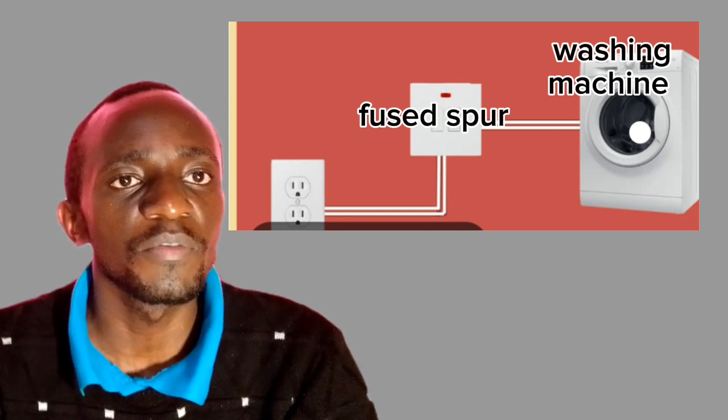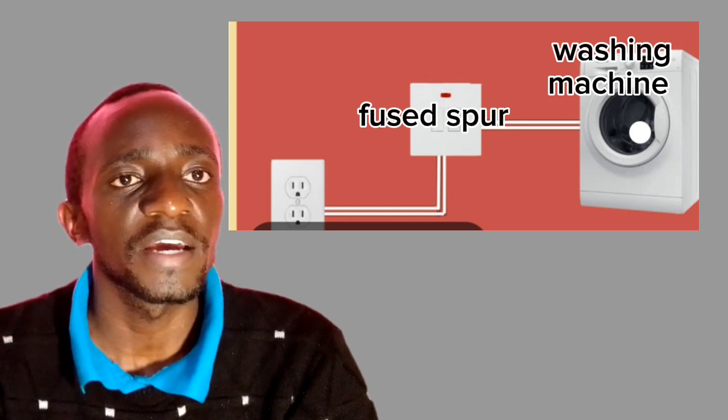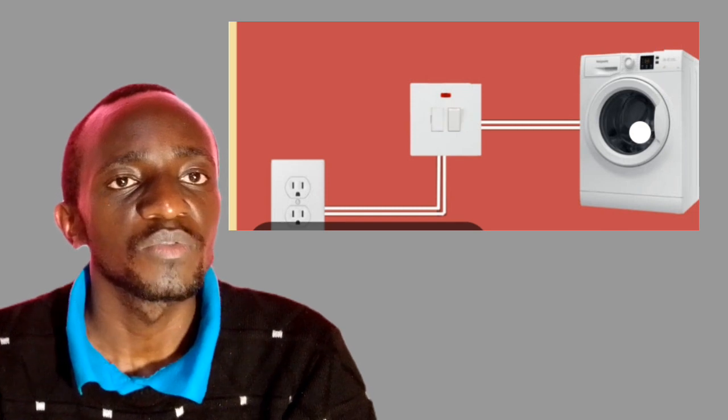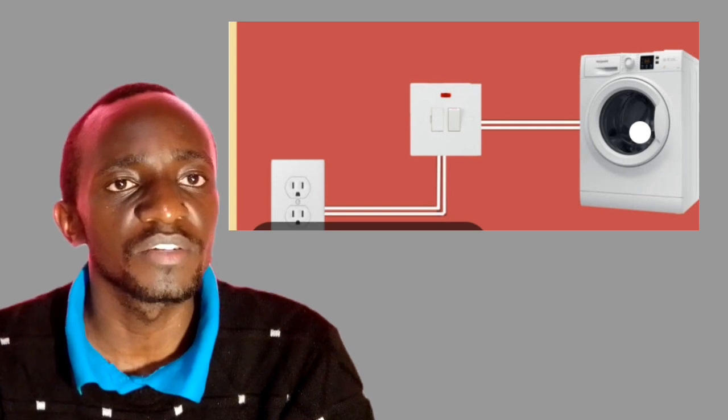We have delicate equipment in electrical work, like cooker units and washing machines, and to avoid having them destroyed by overcurrents or overload, it's necessary to fuse them separately from any other equipment that is using a socket outlet. So in many socket outlet wirings, we tend to do an extension from the main socket outlet, radial or ring, for the purpose of fusing, and it is that extension from the socket outlet that we call a spur.